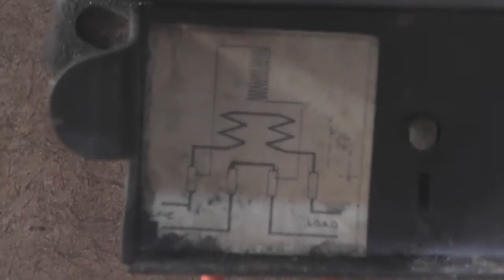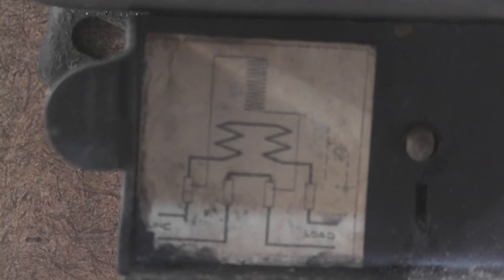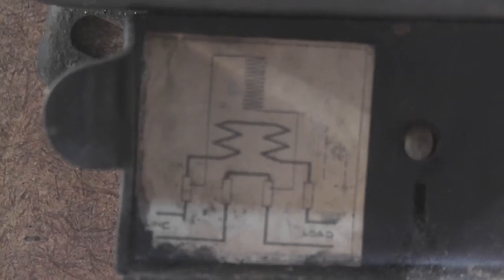The nameplate actually reveals the wiring diagram: active in, neutral in, neutral out, and neutral active out. So somebody could have blown himself up quite nicely wiring this meter up.